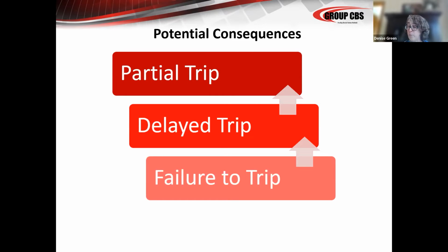At least at that point, the breaker has tripped. So you are isolated, hopefully, to that one area, and the length of the fault wasn't long enough for the main to catch it as well. This is especially hard with ground fault and instantaneous faults. Sometimes an instantaneous fault escalates so fast that if a feeder breaker doesn't trip quickly enough, the main will pick it up and trip as well. So you get into that same situation as the feeder failed to trip and now the main is interrupting as well.